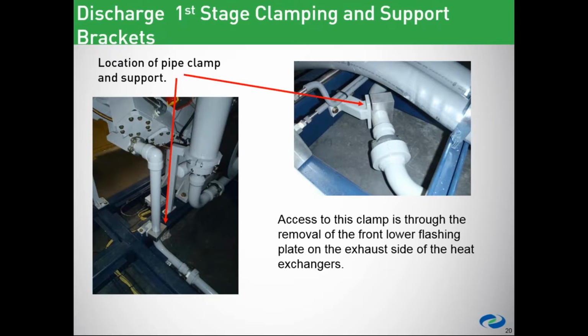So the first stage discharge pipe and its support brackets, it's critical that you know about these. Coming off of the compressor block, we see tubing and a clamp. This clamp is just above the flooring in this access opening, or access corridor, as they're calling it. Basically, you remove that section of flooring and you'll be able to get this pipe spool out. And there's a breaking point between the two sections of pipe spool midway across that floor.